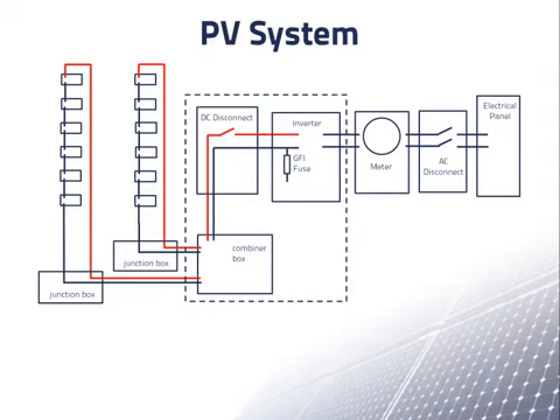Now we'll connect the frames of our first string of modules to an equipment grounding conductor. If we are using WEEB connectors, then part of the equipment grounding conductor is a rail. If not, the rail also needs to be connected to the equipment grounding conductor. Either way, the frames and rails need to be connected to a grounding wire that heads into the junction box. We also need to do the same connections between the rails and frames of the second string and an equipment grounding conductor going into the second junction box.